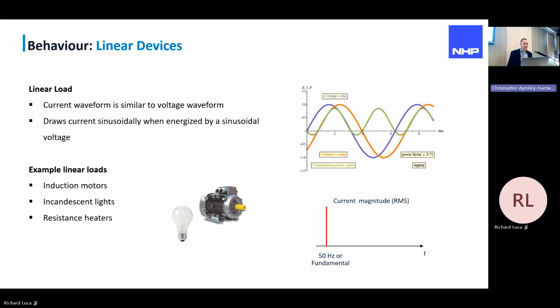When we talk about linear devices, we're saying that the loads that we're connecting to the network, they're drawing a current sinusoidal waveform, which is similar to the utility waveform at 50 Hertz. So there's limited distortion there. We may have a phase shift, which is going to create inefficiencies, and that can be corrected with power factor correction capacitors. But all the load current is drawn at the fundamental frequency, 50 Hertz. And examples there, induction motors, incandescent lights, resistance heaters.